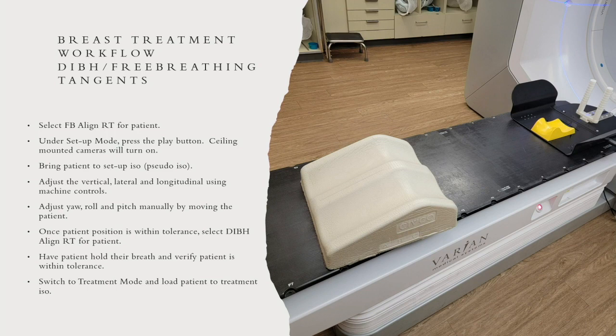So once the patient is on the table, we're going to select the free breathing scan on AlignRT for the patient. Under the setup mode, you're going to press the play button. The ceiling-mounted cameras will turn on. We're going to bring our patient up to setup ISO or pseudo ISO. We adjust the vertical, the lateral, and the longitudinal using the machine controls. And we're going to adjust the yaw, the pitch, and the roll by manually moving the patient.